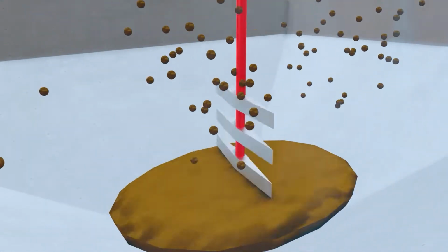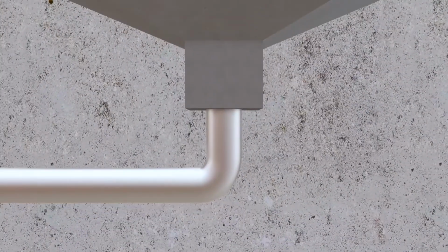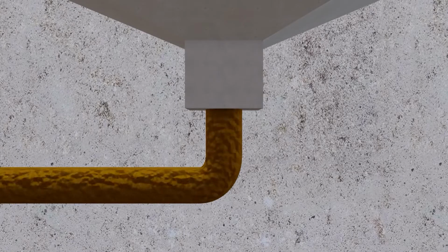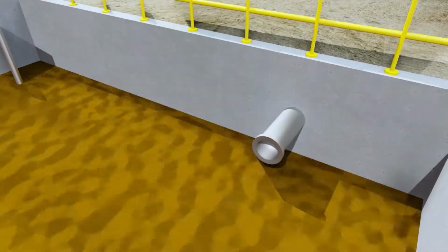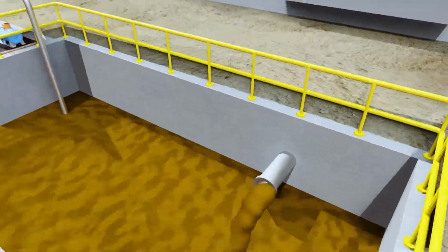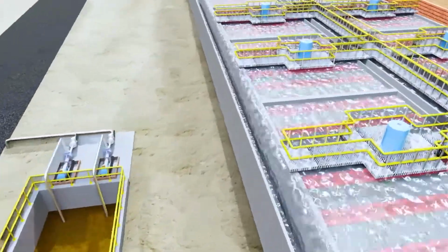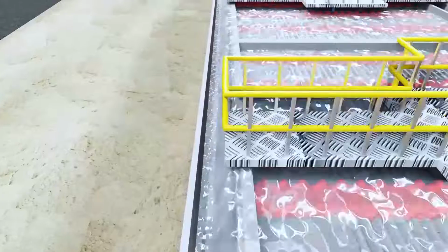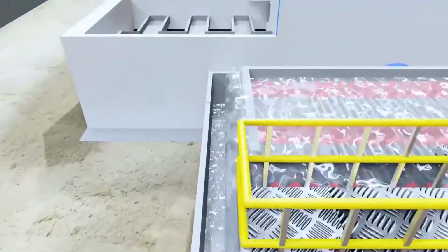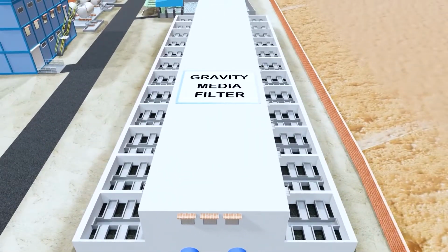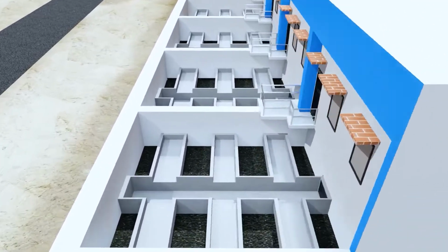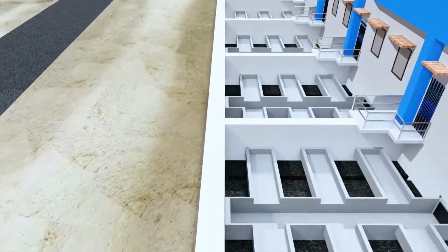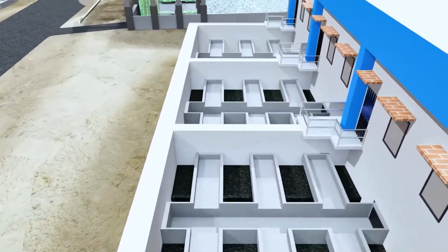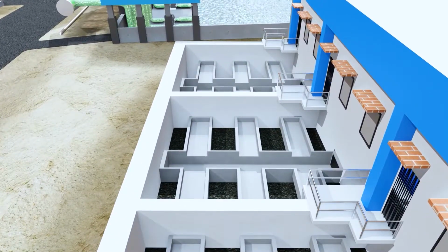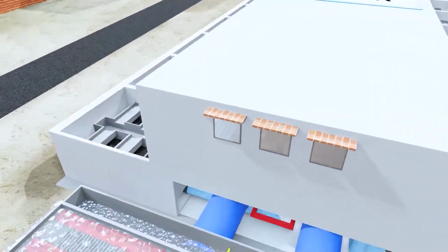Sludge will be formed at the bottom by unwanted particles, and sludge will be moved to the sludge tank via pipeline. The water filtered in the lamella clarifier will overflow and will move to the gravity media filter via a channel. In the gravity media filter, there are in total 24 beds. Gravity media filter uses gravity as the motive for a fluid stream to pass through a bed of granular media through which removal of impurities is achieved.